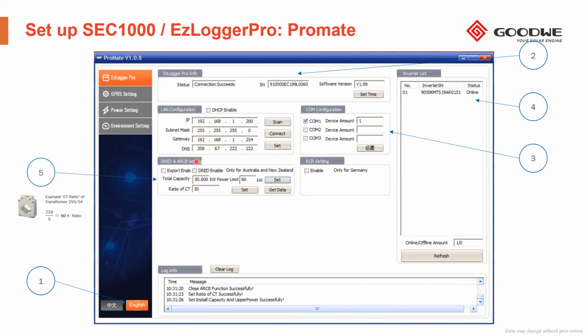In this case, almost at the end of this setting up, in this box, we have to input the total capacity of the PV system, and the power limit in this case is above the limit, so we input 60. And the rating of the CT is also relevant. We have here an example. If we use, for instance, a 250 amps in the primary circuit coil, and 5 amps by default in the secondary, actually the result is 50. This is what we need to input here, right?